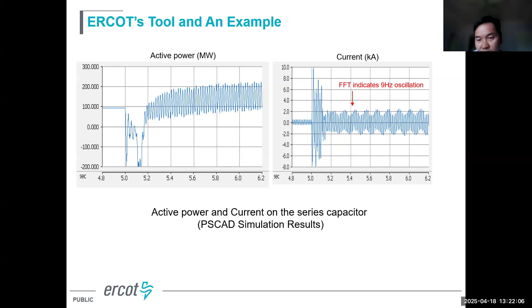However, even after we do these kinds of studies and require the new IBRs to go through the SSR studies, we still have a few SSCI events. These are the events in South Texas in 2017, and they are all related to radial connection conditions. You either trip the line between station 4 and station 5, and then these two power plants become radial to the series compensation, or you trip the line between station 2 and station 3, and then these two wind farms become radially connected to the series compensation. We had 3 events, with either undamped or damped oscillation. Basically, SSCI events happened, and all the wind turbines here tripped because they have SSCI protection.